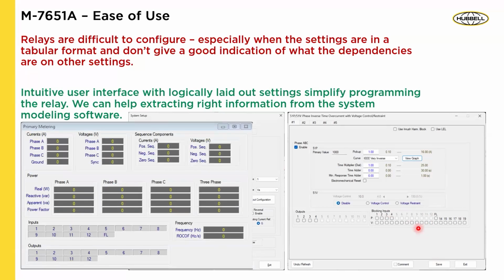Same with metering. You'd see the currents, voltages, they're separate. The sequence component is separate. You could see the power, all three power, your inputs, your frequency, your outputs, right? So you're no longer having to shift through a table of values and try to figure out where I have to stop looking to find out where the phase B power is for the reactive power, for example.